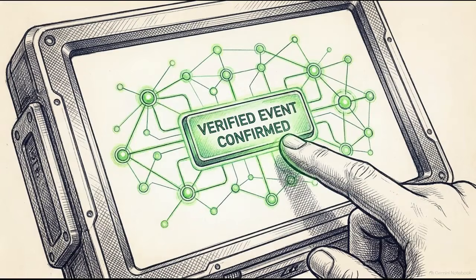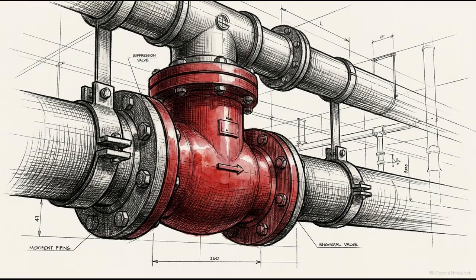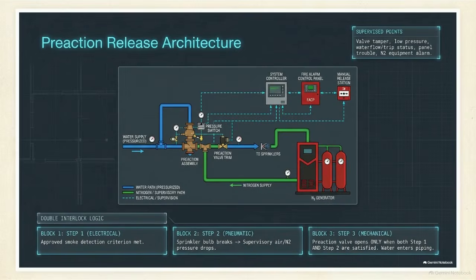Once the digital state machine confirms an event, it has to physically actuate the suppression hardware. In a data center, releasing water or gas requires absolute certainty. This piping schematic details a double interlock preaction architecture. The pipes above the servers are filled with pressurized nitrogen, marked in green, holding back the pressurized water supply, marked in blue. To release water, two independent blocks must be satisfied.